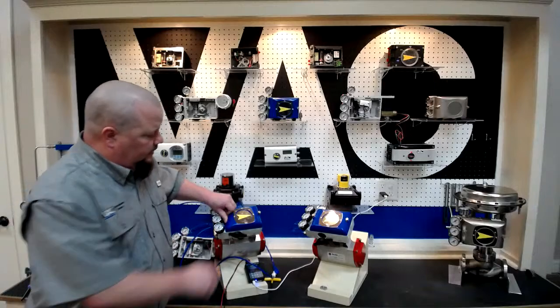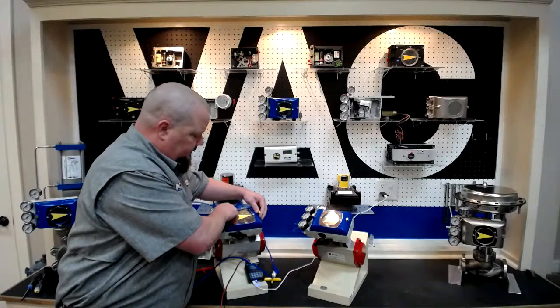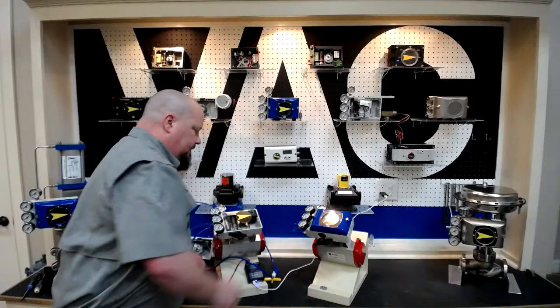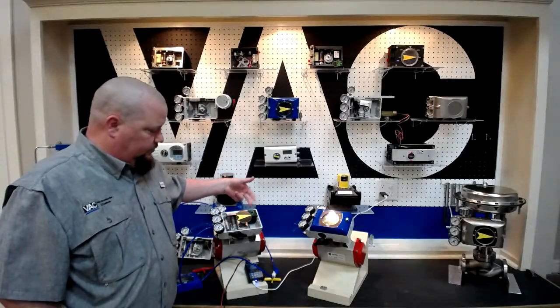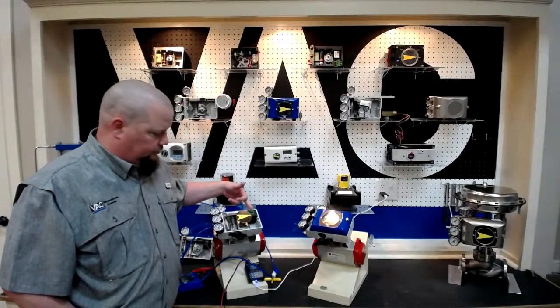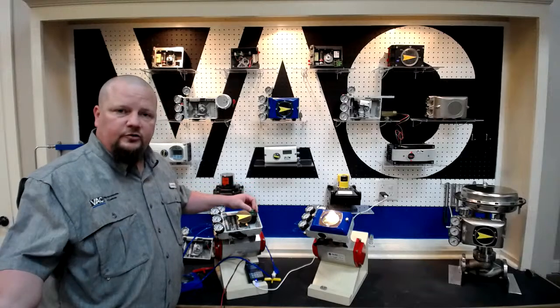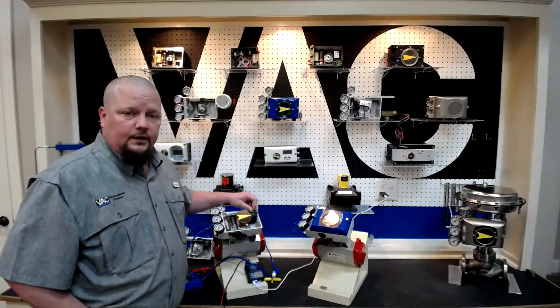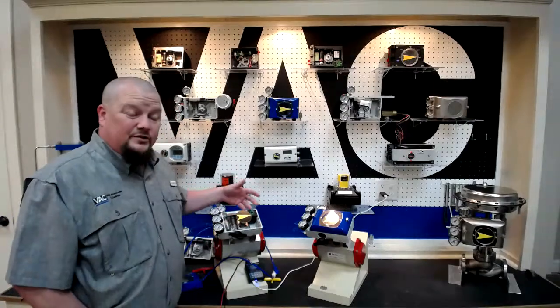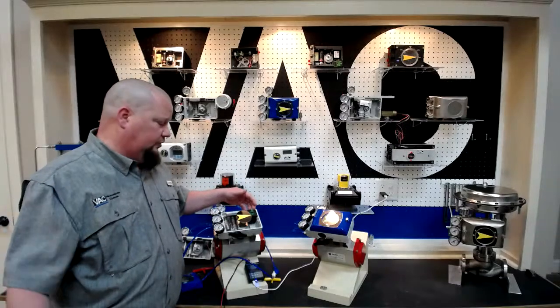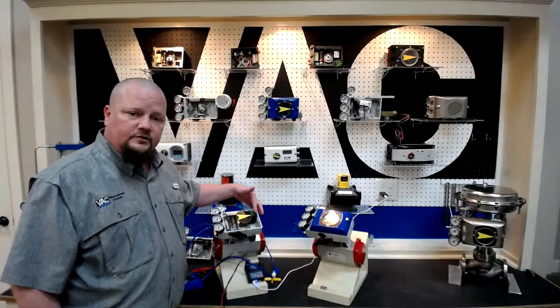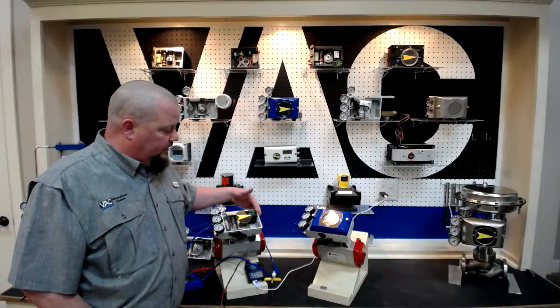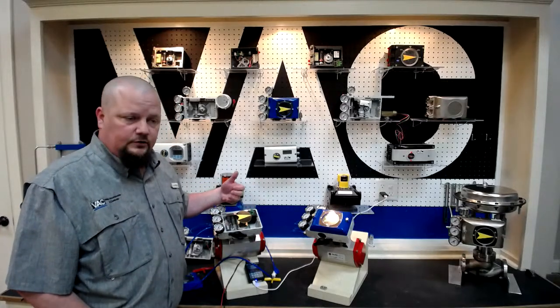Another issue: on our IDPs, the control room has wires landed to the terminal strip, and they're supposed to be giving us a 4 to 20 milliamp signal. We can't always guarantee that, and we can't just assume that. So we actually have test points on the V200 here where we can test what the actual incoming signal is.